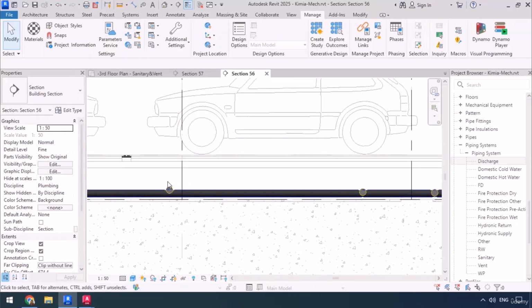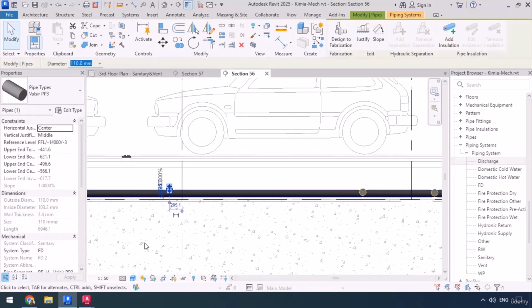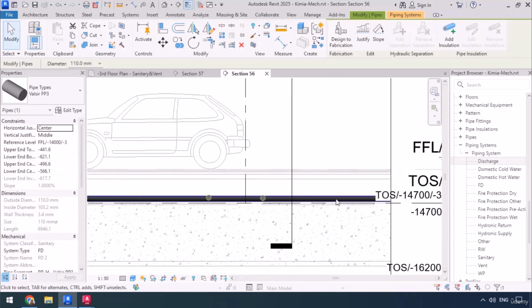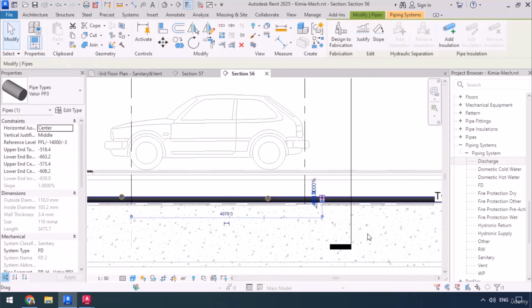So one thing I can do is I could raise these pipes and basically have them at a higher elevation, and also considering that they are sloped pipes, they can go higher. Or instead I could move this pipe above them. But anyway, I recommend that you reposition the sloped pipes because their slopes might save some interferences, and that also saves you from making drastic changes to the elevations.